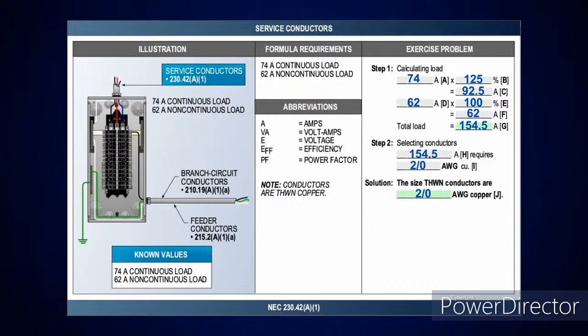I've got 74 amps of continuous load. Take it at 125%, gives me 92.5 amps. I've got 62 amps of non-continuous load, naturally that's 62 amps at 100%. Add it together, it gives me 154.5. Now, a 1-aught is good for 150 amps, but we have to be above the 154.5 amps. A lot of times I would tell people to just round this up to 155 amps. The next conductor size above that in the 75 degrees C column would be a 2-aught conductor, which is good for 175 amps. Pretty simple.